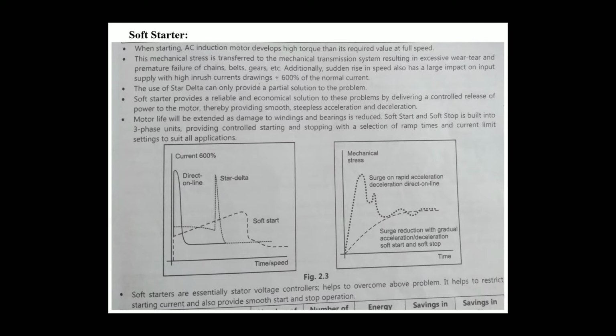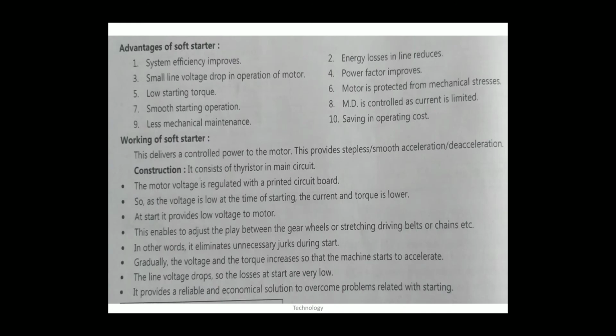But in soft starter, the waveform at the time of starting shows the current increasing normally, then slightly increasing, and then decreasing. That's why most industries use the soft starter. Soft starters are essentially stator voltage controllers that help to overcome the above problem. They help to restrict starting current and also provide smooth start and stop operation. Next, advantages of soft starter.